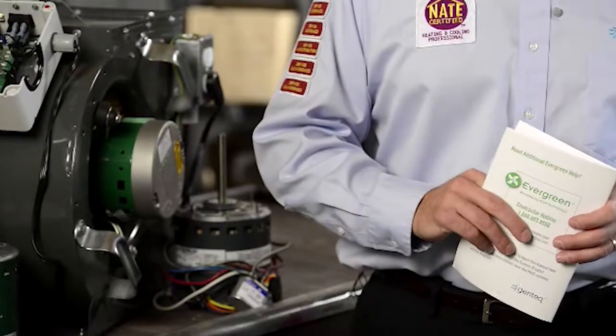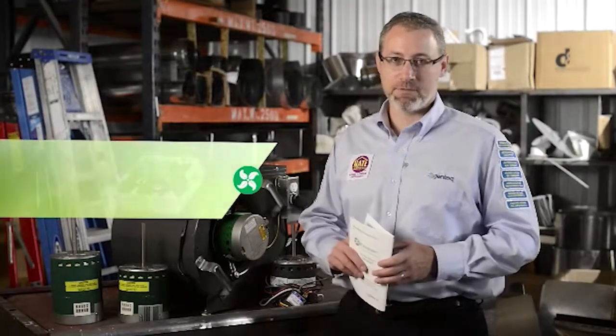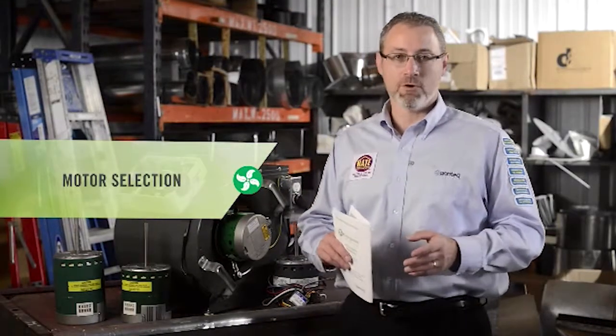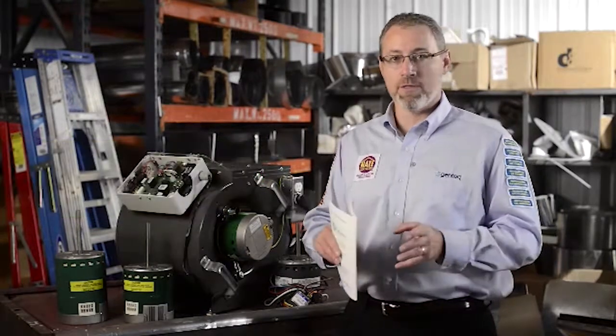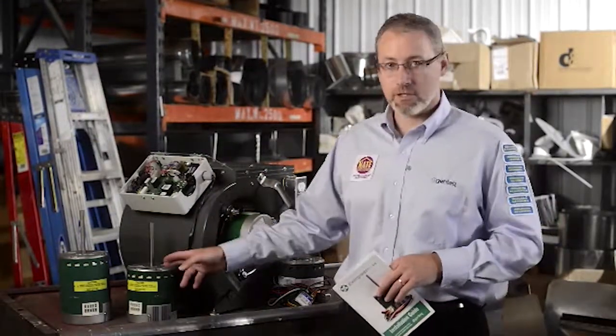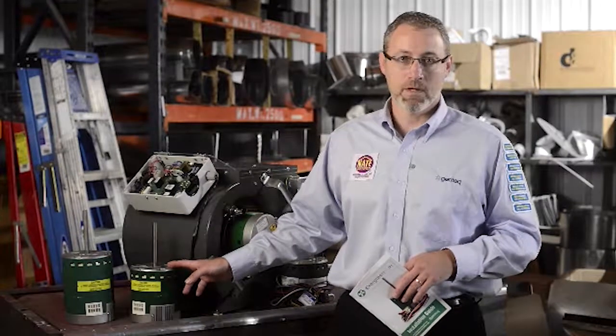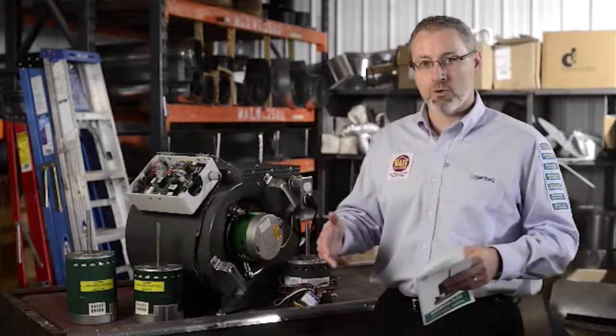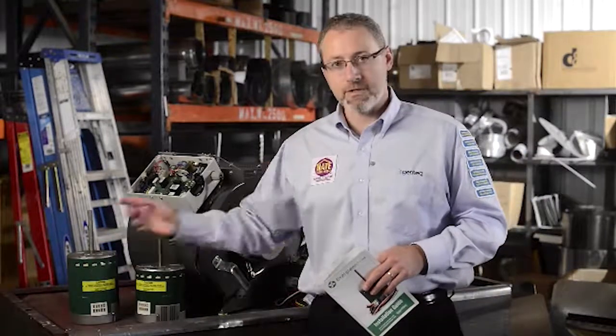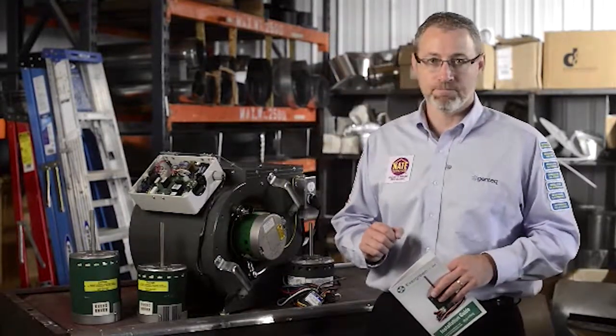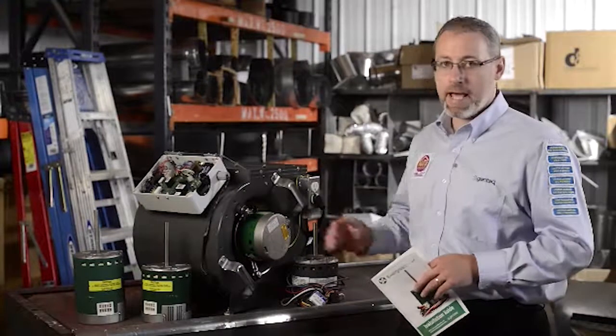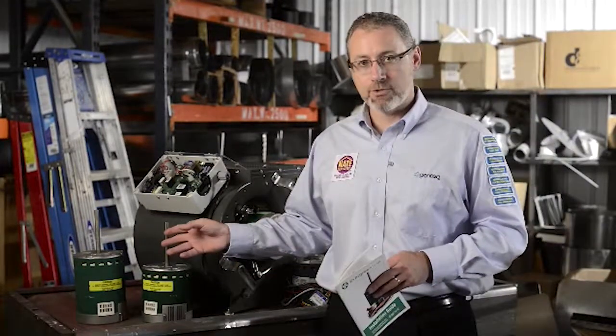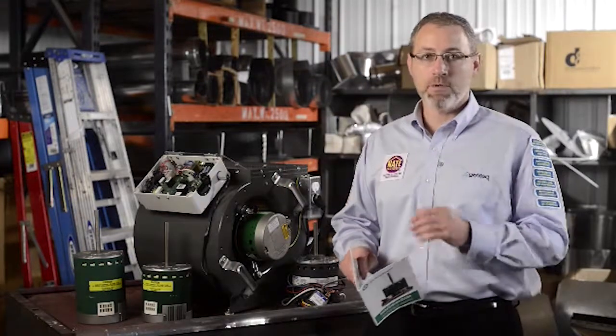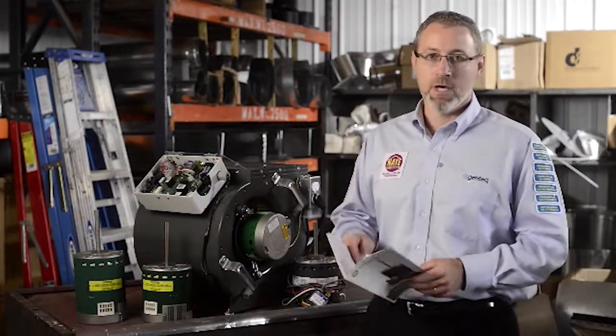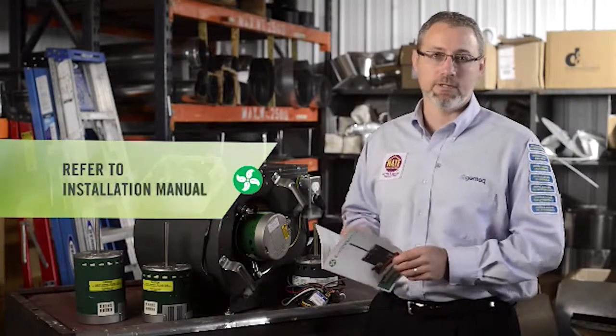With two multi-horsepower products, selecting the correct replacement motor is very easy. If your old motor is 1/5 through 1/3 horsepower rated, you're obviously going to use the 1/2 horsepower motor. If your old motor is 3/4 or 1 horsepower rated, you're obviously going to use the 1 horsepower motor. If your old motor is 1/2 horsepower rated, you could actually use the 1/2 or 1 horsepower motor. To help you get the right motor for your application, we provide a selection guide in the installation manual.